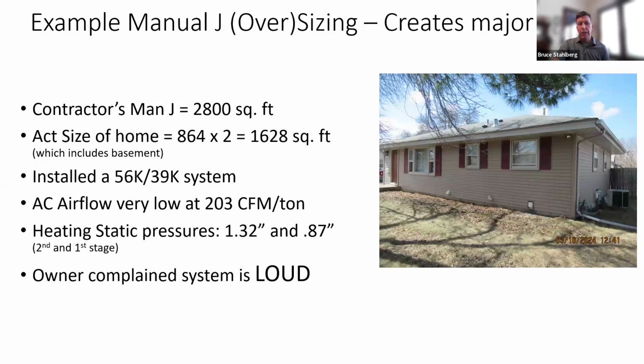Here's another example. The contractor's Manual J used 2,800 square feet. This was a simple Rambler home, not that big. So I went out and measured it. 864 square feet per floor. Now, I actually included the basement, which I wonder whether we need to give the same amount of weight. But at any rate, I used that number. The contractor installed a fairly large furnace, a 60,000 BTU unit. It was two-stage. I measured the airflow.